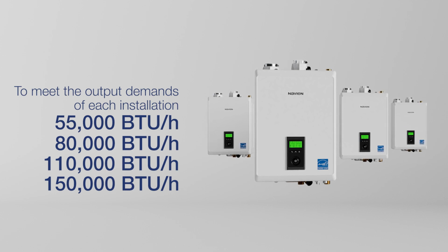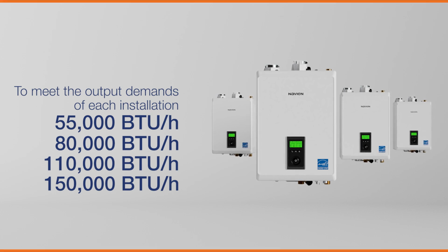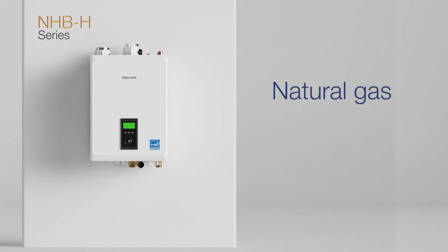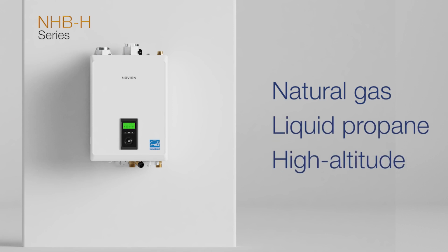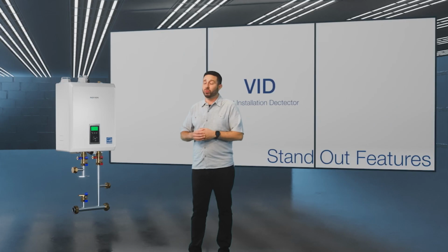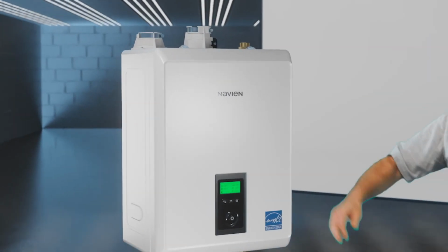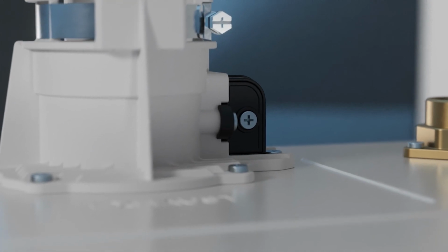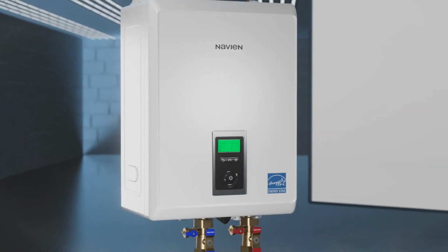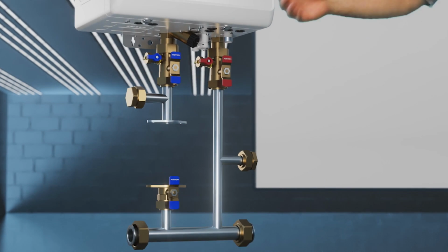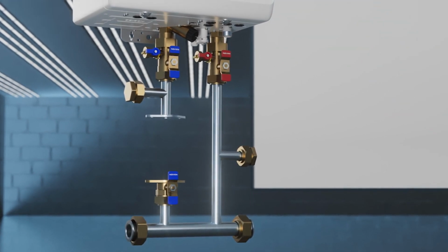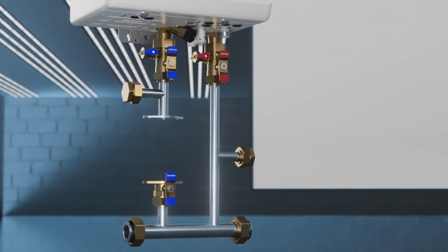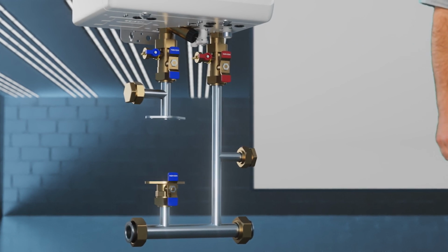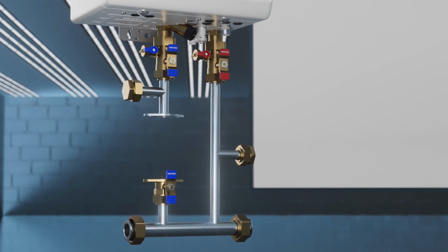Up to 16 units can be cascaded, and up to 8 units can be comb vented, saving installation time and costs. They can be converted for use in natural gas, liquid propane, and high altitude installations. And each unit comes pre-installed with a vent installation detector to support proper vent installation. We also made installation easier on you by making an all-new stainless steel primary manifold. This kit, available for each model, replaces the need for building a primary loop and simplifies the installation of indirect tanks.